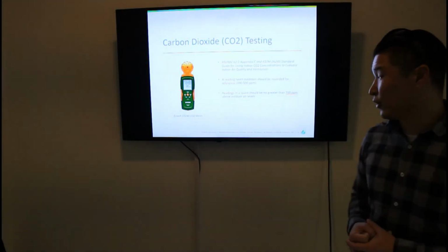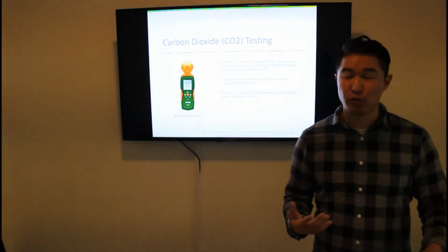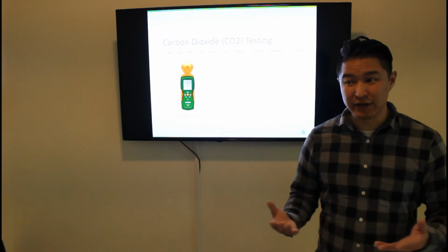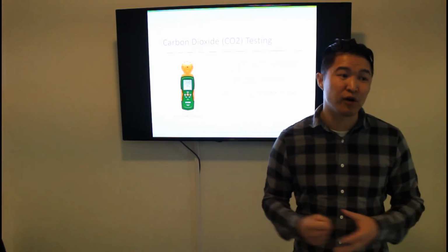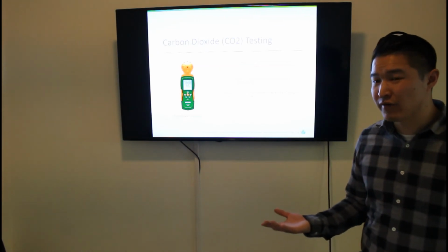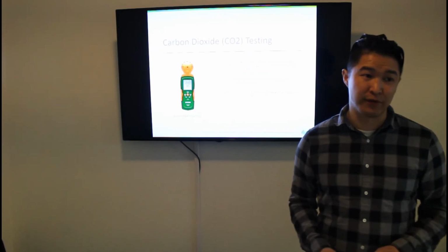One time I was doing a measurement in an office space, and I believe I went in during their lunch hour, I would get readings that were like 1,200, 1,300 parts per million. But typically you're going to see in a lot of office properties readings in the range of like 600 to 700 parts per million.